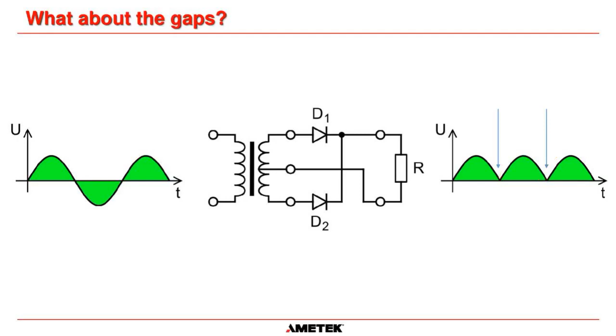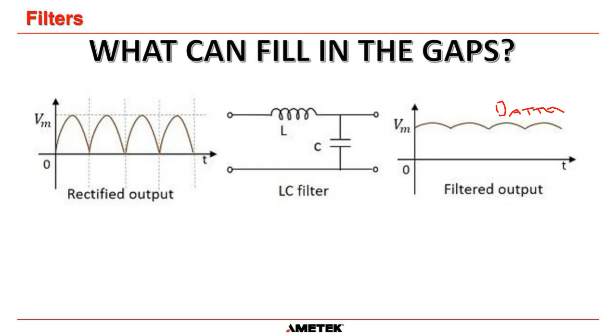And the way that we do that is we use an LC filter. L is for inductance, C is for capacitance. So you can see on the left-hand side, this is our rectifier output on a single phase system before it goes into an LC filter. What the inductor and capacitor do together is basically fill in the gap. On this circuit here, because it's a sine wave, it's doing that to the output of the system, filling in those gaps. So instead of seeing that waveform there, we're seeing a much flatter DC output, and a battery would be able to tolerate that level of ripple on a system.